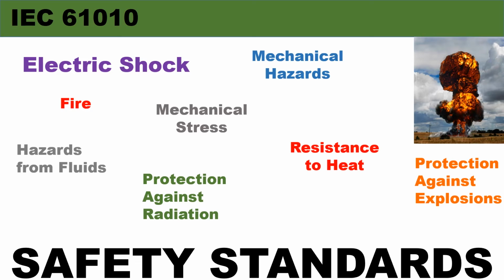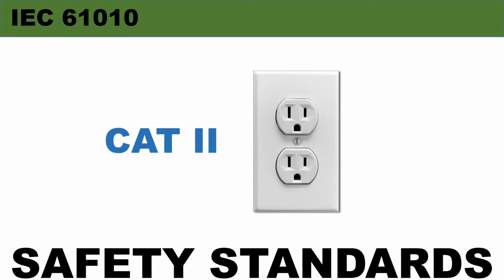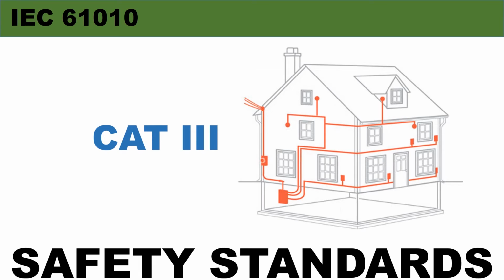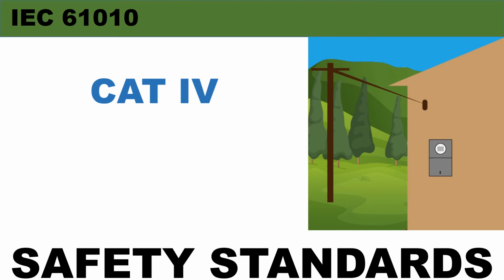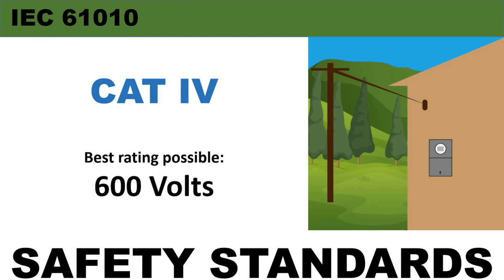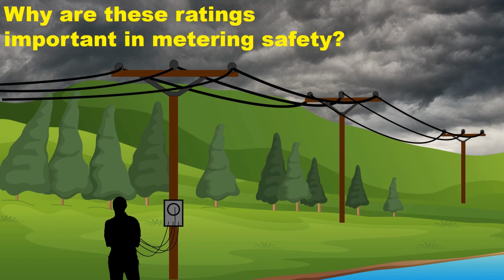That safety standard has classified electrical hazards into categories. Category 2 represents the hazards you find at the electrical outlet level. Category 3 represents those found in circuits between the outlet and the meter. And Category 4 represents the hazards you will be dealing with most often at the meter to the lines at the pole. The highest safety rating a handheld meter testing device can have, according to IEC 61010, is Category 4, 600 volts. So what's the big deal?